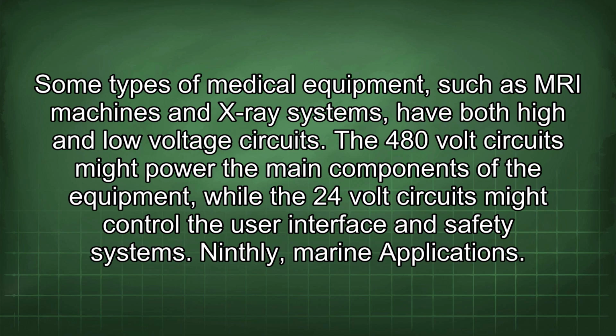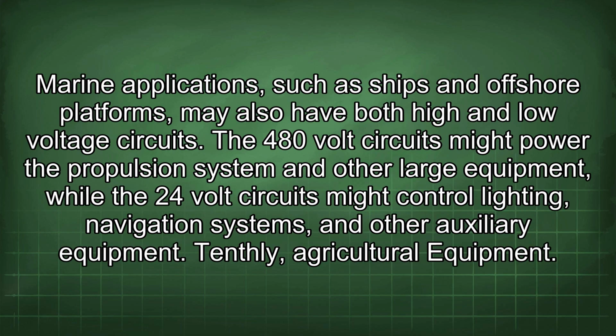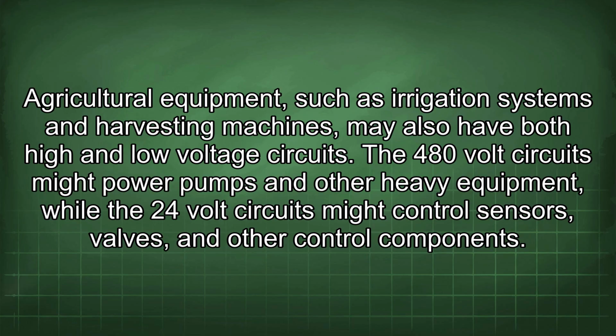Ninthly, marine applications. Marine applications, such as ships and offshore platforms, may also have both high and low voltage circuits. The 480-volt circuits might power the propulsion system and other large equipment, while the 24-volt circuits might control lighting, navigation systems, and other auxiliary equipment. Tenthly, agricultural equipment. Agricultural equipment, such as irrigation systems and harvesting machines, may also have both high and low voltage circuits. The 480-volt circuits might power pumps and other heavy equipment, while the 24-volt circuits might control sensors, valves, and other control components.